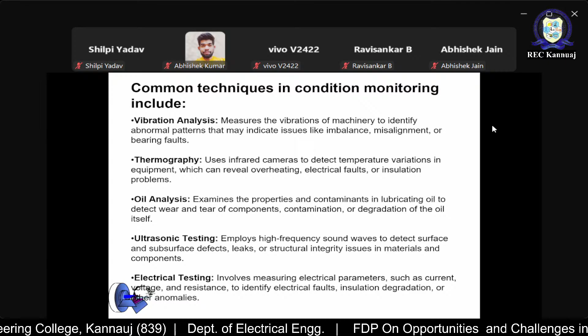So these are the technologies, but we cannot use every technology for all types of faults. Some technologies suit some faults. Vibration can be used for bearing damage, rotor bar broken, and air gap eccentricity. MCSA, motor current signature analysis, is used for stator winding along with the vibration. With the help of MCSA we can detect stator winding faults, along with air gap eccentricity, rotor bar broken, and bearing damage.